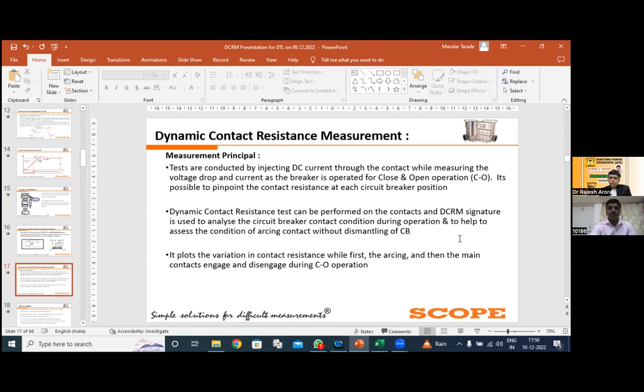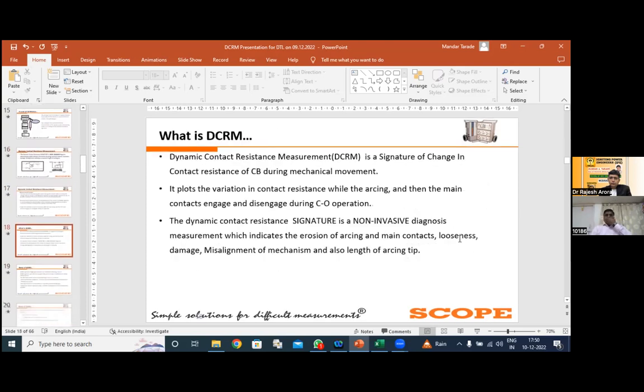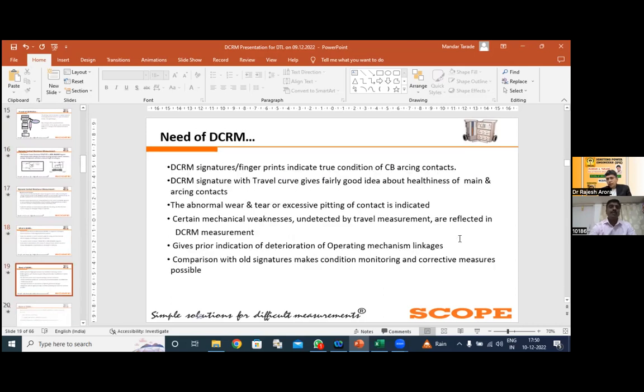Before telling you the measurement principle of the DCRM, let me tell you the need for the DCRM. The DCRM signature with the travel traces will give you a fair idea about the healthiness of the main as well as the arcing contact. It will also tell you about abnormal wear and tear and excessive pitting of the contact. Certain mechanical weaknesses that are undetected by the travel measurements are simply reflected in the DCRM measurement. It will also give you a prior indication of deterioration of the operating mechanism linkages.